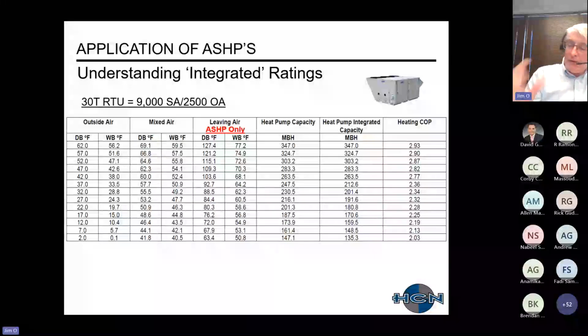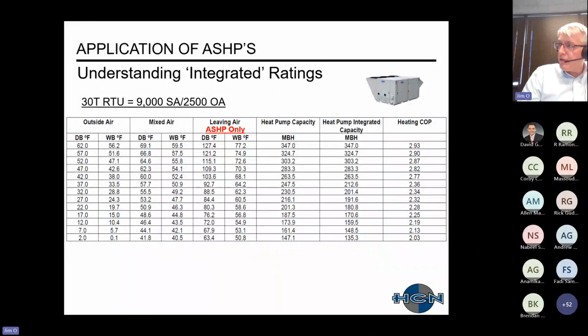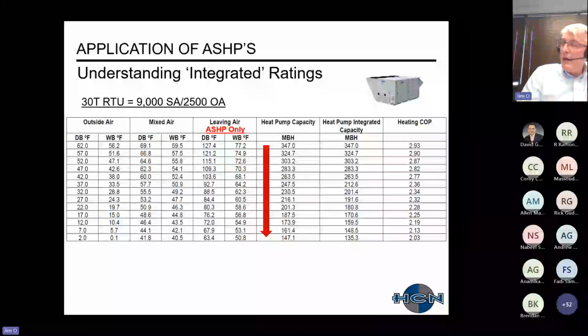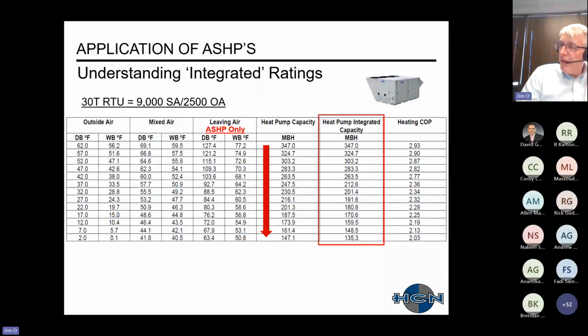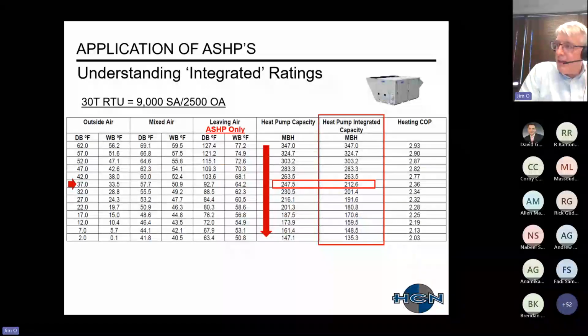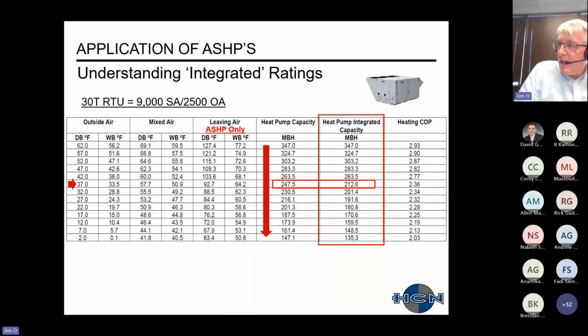There's an integrated capacity that I'll explain next, and then also there's our coefficient of performance. I just want to reiterate once again that as our ambient temperature drops, we're going to reduce our heating output. You can also see that our coefficient of performance has also been reduced. Now, what is integrated heating capacity? If you do a comparison at the different bin temperatures, you can see that the integrated heating capacity has a lower output capacity versus the standard heat pump.